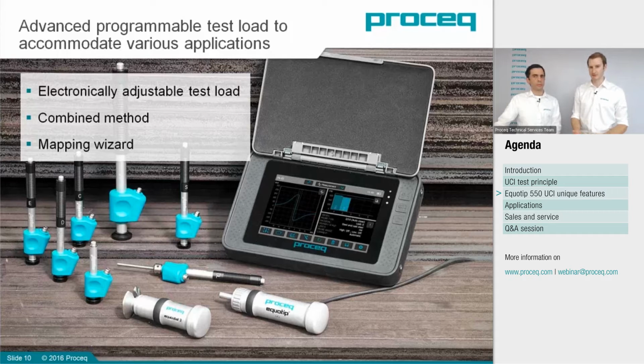For example, UCI is material dependent. We just said you have to calibrate it for your material if it's not standard steel, and this has to be done with a test block with a known hardness value. But if you don't have such a test block, you can also combine UCI with portable Rockwell, since portable Rockwell is material independent. Therefore, you can combine the advantages of each method into one very nice, fully portable hardness testing solution.